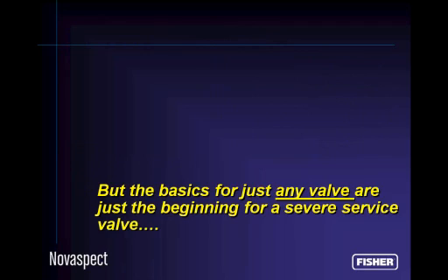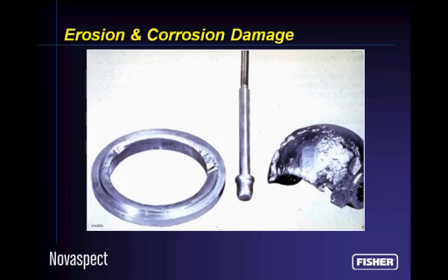But the basics that I just discussed, which apply to any control valve in your plant, are just the beginning of the things we need to worry about for a severe service valve. Yes, we need to worry about all of those things, but in addition, we've got concerns about erosion and corrosion damage. I have some pictures of some parts here that have been damaged by erosion and corrosion. They generally look really nasty. They can fall apart quite quickly. We need to find ways to combat this.